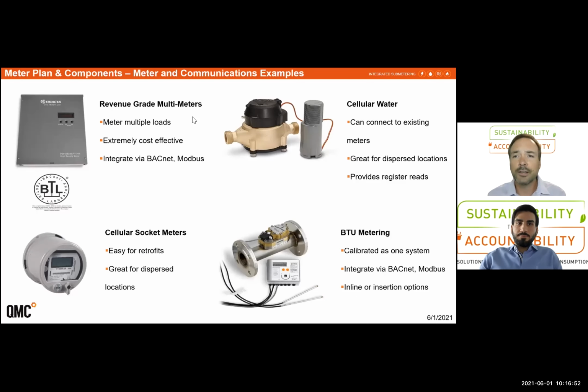Just a quick touch on a few different meter technologies in the market right now. I'm going to get a little bit more into multi-meter point technology because it's used in most buildings now, but not fully well understood. These cellular socket meters are a great meter for metering dispersed loads where you have old glass meters. You pull that out and put a new cellular-enabled meter in, and that's immediately communicating to the cloud without any advanced infrastructure needed on site.